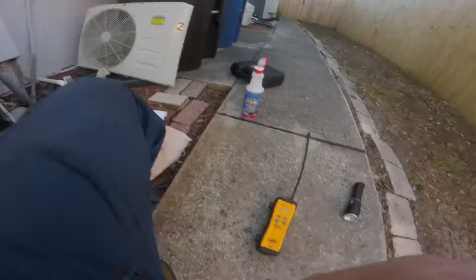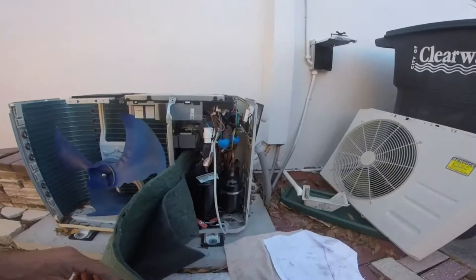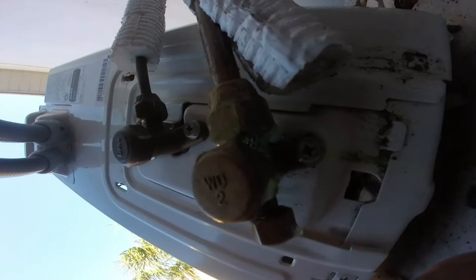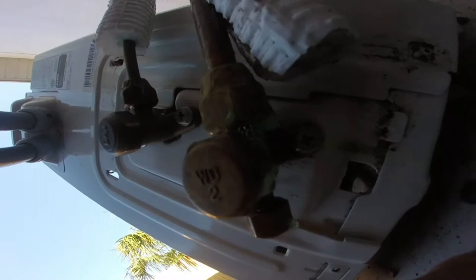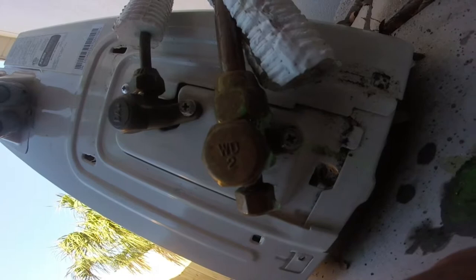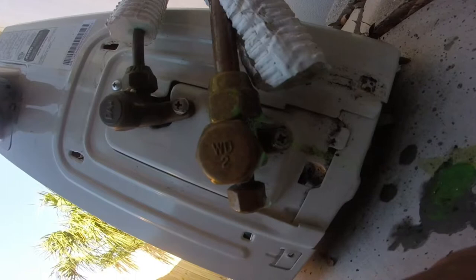So what we're finding on this leak — that's the Fieldpiece, man. It seems to work, it does pick up the leak. I don't know how well you guys can see it, it's making a bubble right now. It's hard to see. I fixed the leak on this line once before; another guy found the thing leaking again. Something's up with this copper — we're gonna see.